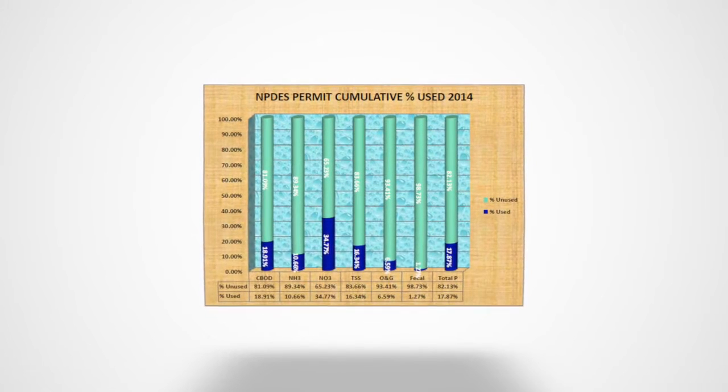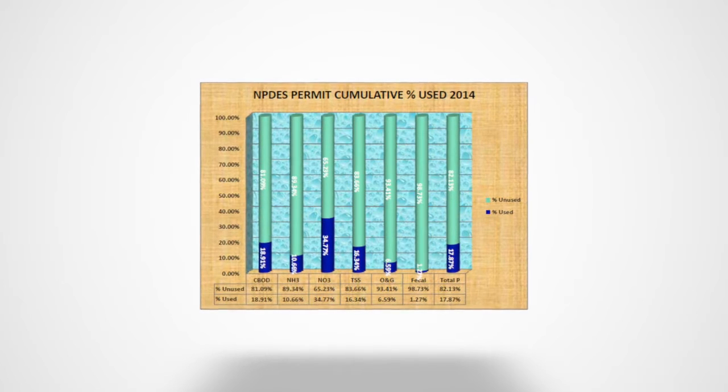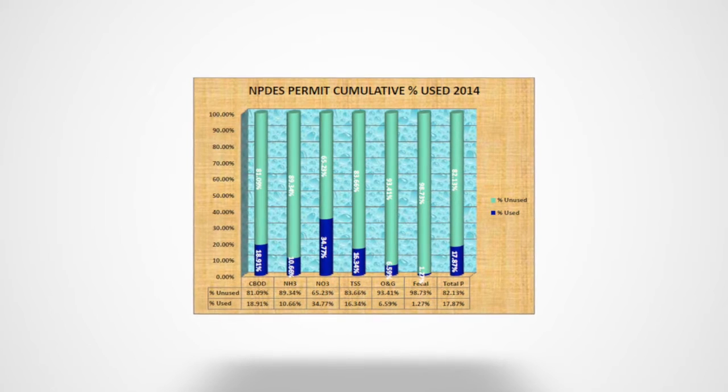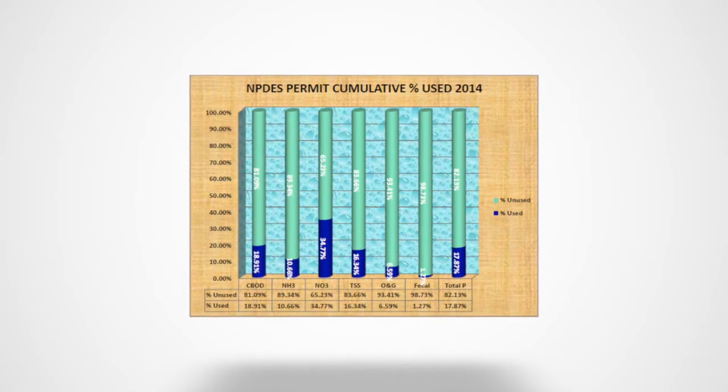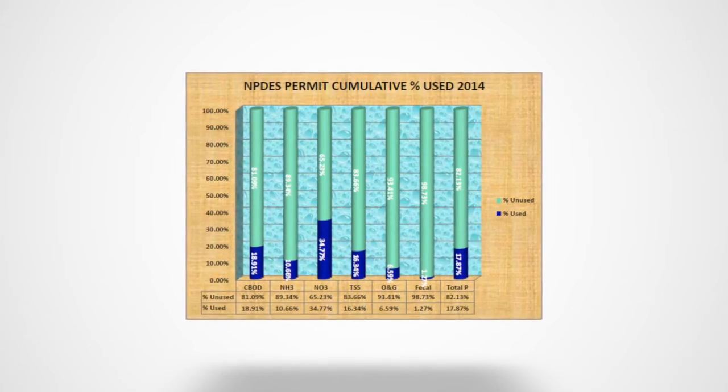Our nutrient limits in our current permit are a phosphorus of 1.0 milligram per liter and a ammonia of 2.4 milligram per liter in the summer. We've been able for the last 15 years to successfully stay below those numbers by a significant threshold. For example, last year we averaged below 0.05 phosphorus going out through the stream, and our direction from the chairman of the board and other management and staff at the company is always to make the best water that we can make. And so we're not looking at permit limits per se, we're looking at what can our treatment plant do and how can we do the best that we can with that process.